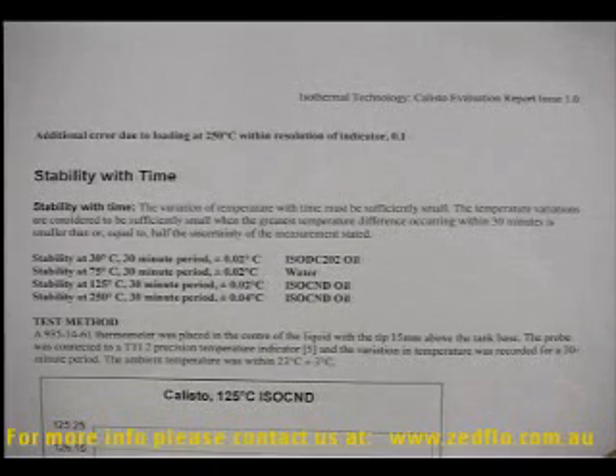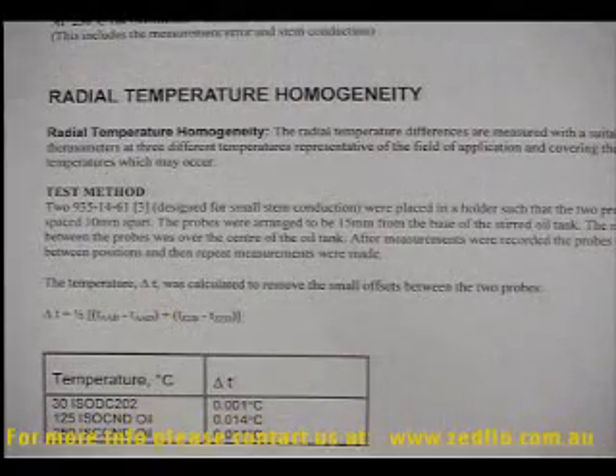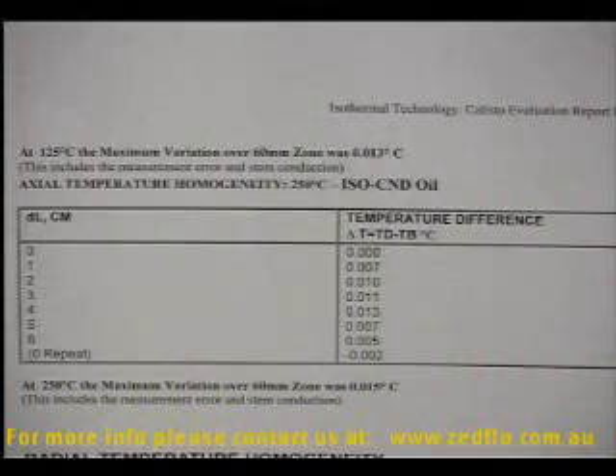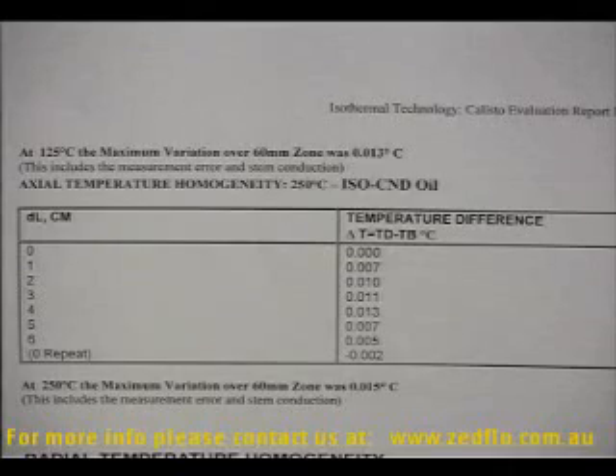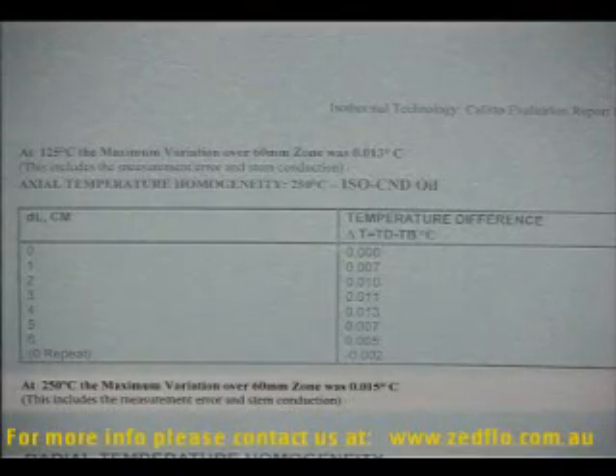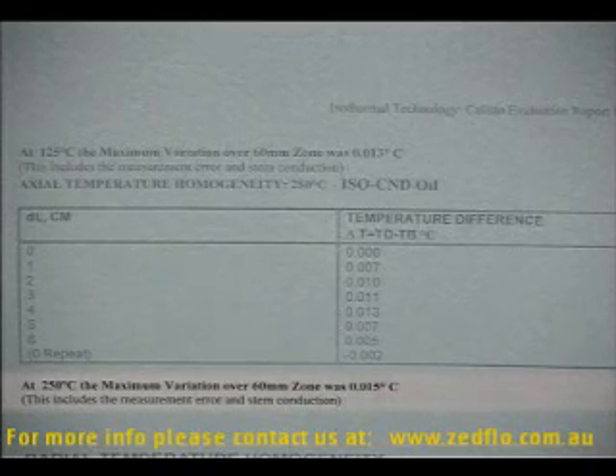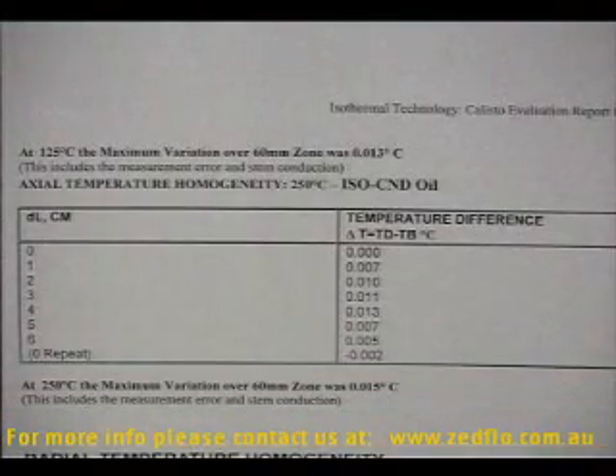Most of the parameters used by the stirred liquid bath on the Isocal 6 are quite similar to those used in the metal block bath. With the metal block insert, the absolute stability is very similar, and the radial temperature homogeneity is very similar. What is different, and what is a great improvement in the stirred liquid bath, is the vertical gradients, as you can see here at 250 degrees Celsius. The variation over a 60 mm zone was only 15 millikelvins. This is some 10 times better than the immersion characteristics in a metal block bath.